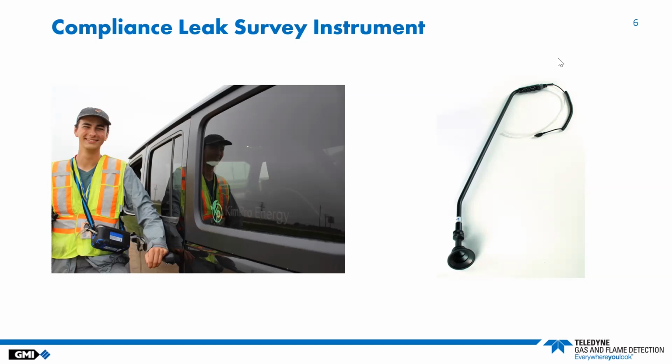If a non-hazardous leak is found, typically known as a class or a grade 2 or 3, then it's scheduled for repair and the leak is monitored to ensure that status does not change. Leaks identified on a utility system are investigated and graded in accordance with local regulations. Grading of a leak will vary by country, state, or province and local utility structure.